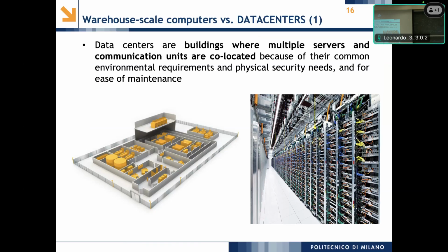Be aware that we have a small server room, I think 40 square meters, where we plug all our stuff. Just the empty server room, just the non-redundant cooling, 10 years ago cost €500,000. So for the empty server room, because you have racks, you pay the cooling, and then you also have issues in case of fire, and so on. So there is a cost in the building too, as we will see.